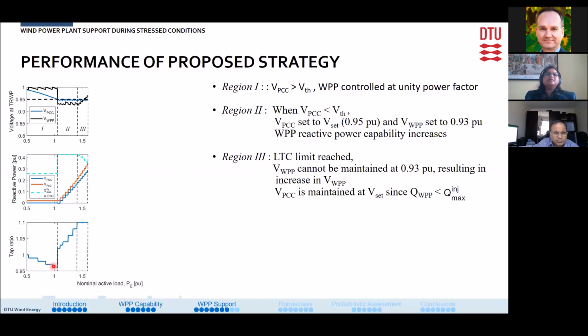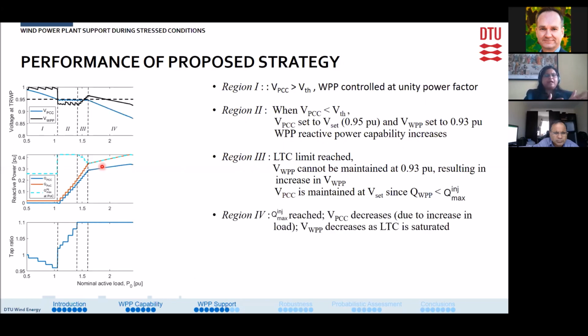Next, the taps of the wind power plant transformer get limited. They reach the maximum limit. Therefore, the wind power plant voltage cannot be maintained at 0.93 pu, and it starts to increase as seen here. However, we see that the PCC voltage is still being maintained at the set point. That is because the reactive power requirement to achieve that voltage is still less than the reactive power capability of the wind power plant. In all these cases, we have simulated the load continuously increasing in the system. So with further increase in load, what happens?